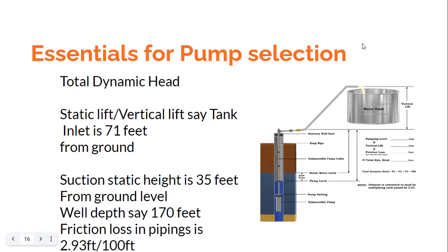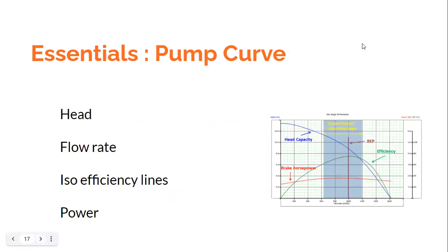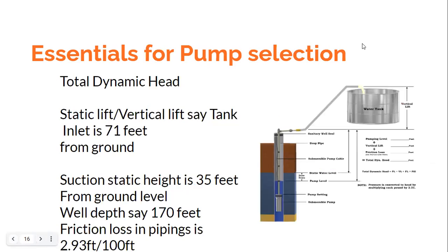If you take measurements in feet, total dynamic head will be in feet; if in meters of water column, you get meters of water column — use whatever units your country follows. This discussion about the system — vertical lift, pumping level, and frictional losses — is known in scientific terms as system characteristics.